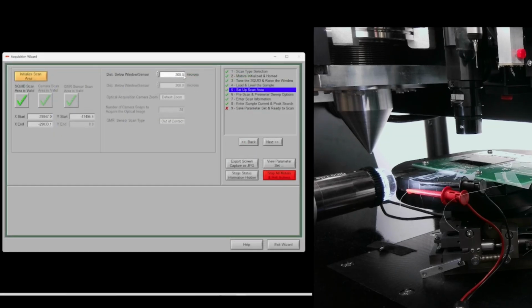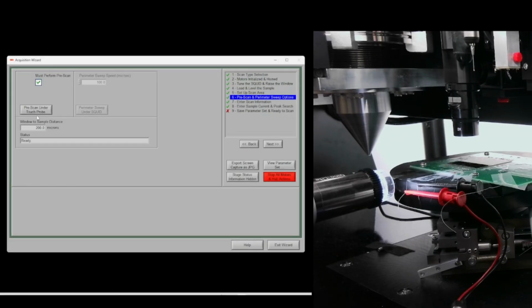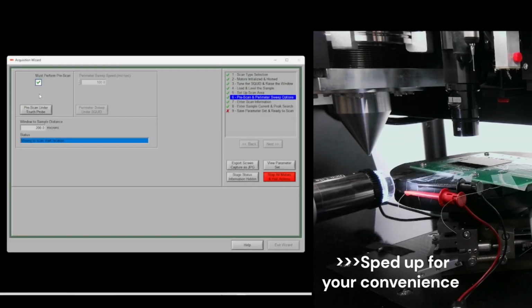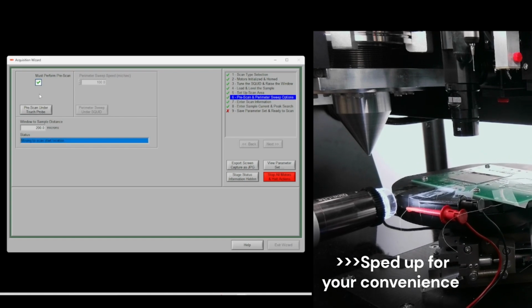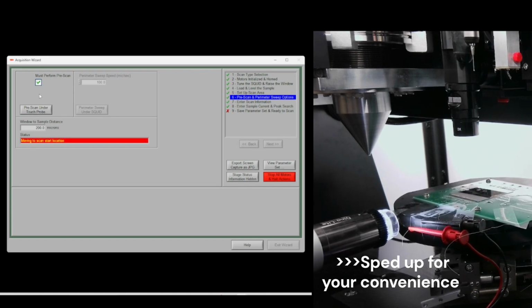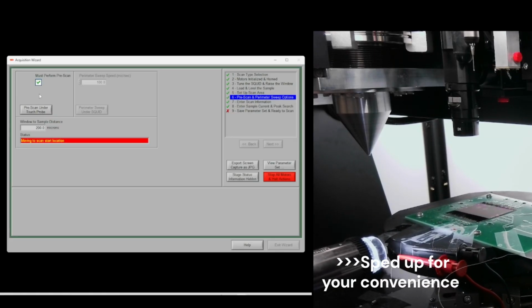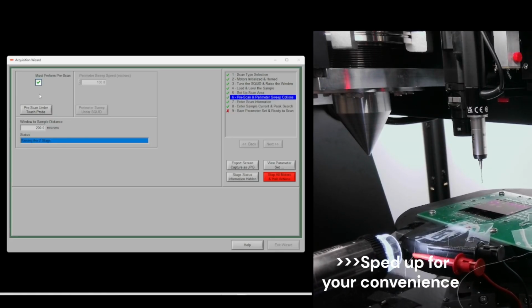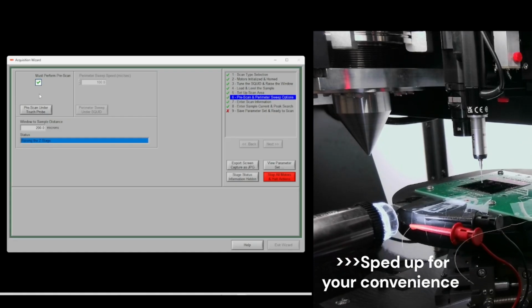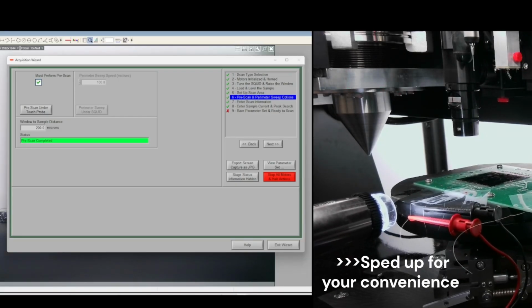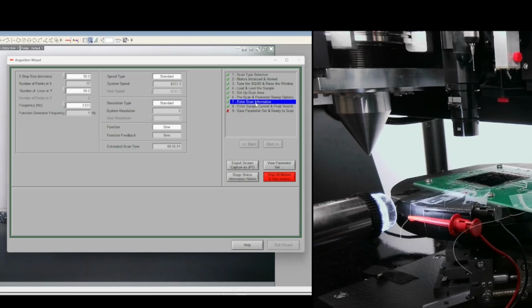We now confirm the distance below the window is set to 200 microns, as required. With position complete, we perform a pre-scan under the touch probe using the Dino-Lite camera to visually confirm there's no contact with the sample. If everything looks clear, we continue to Step 7 so that before starting the scan, we adjust the X step size to 10 microns and ensure the Y line count is set to 50.